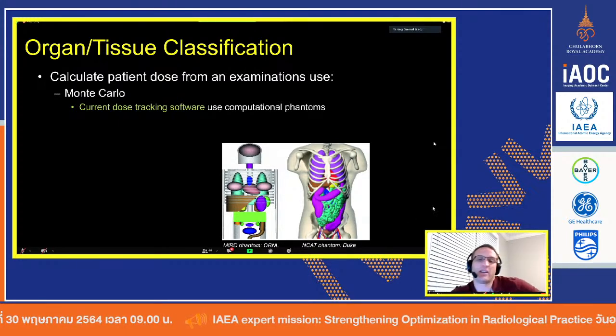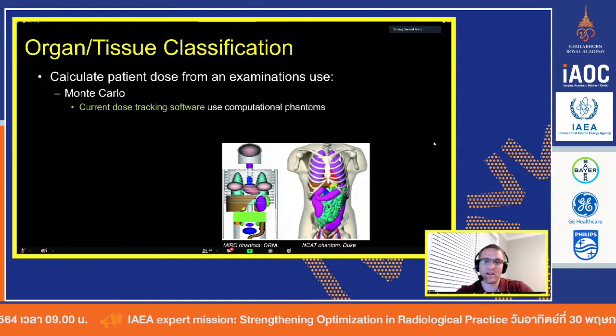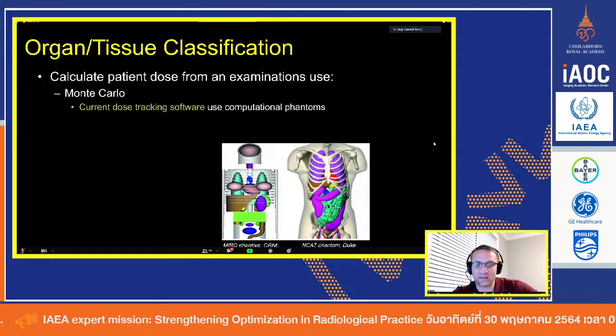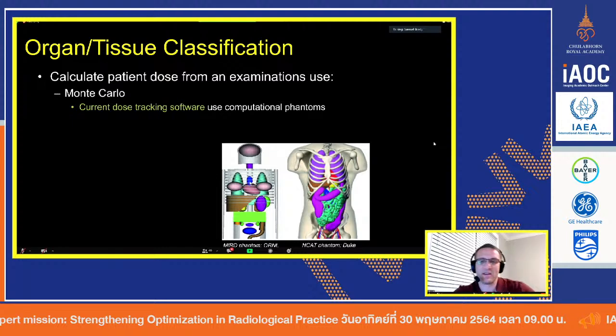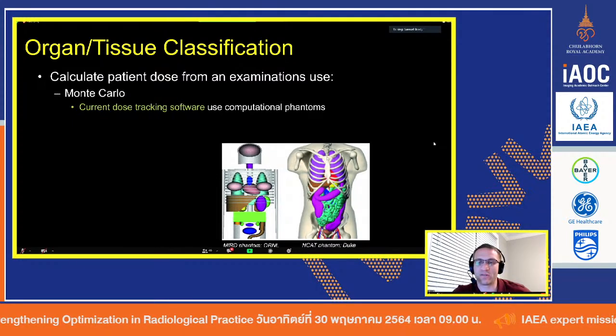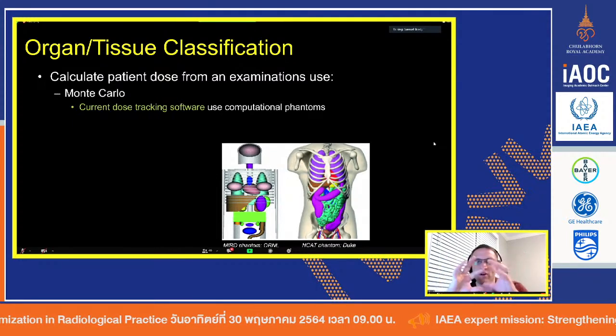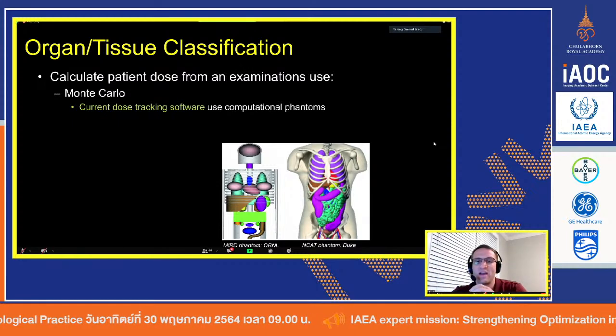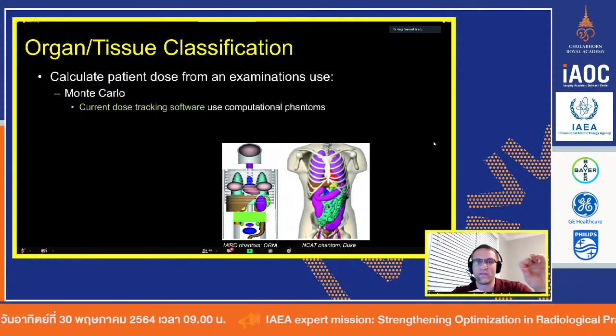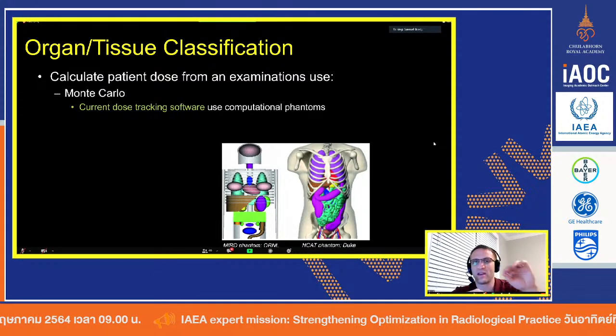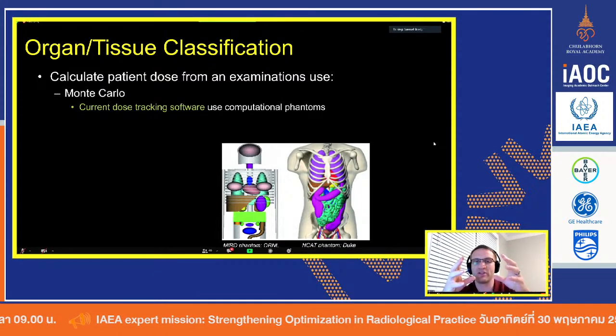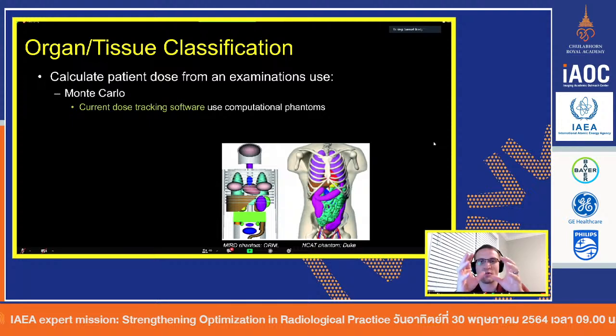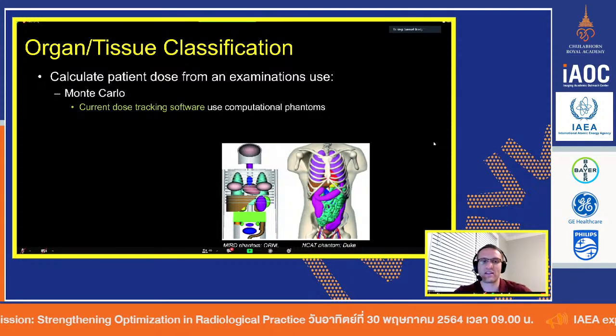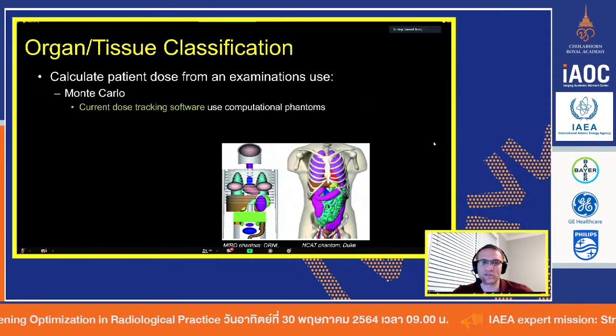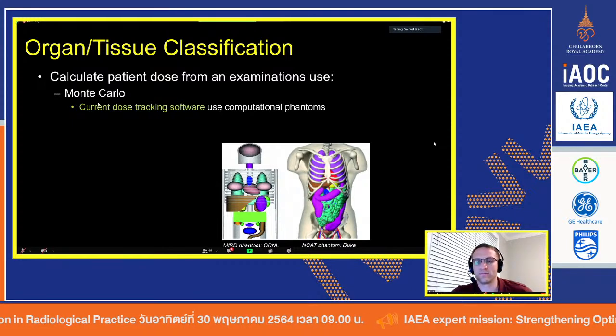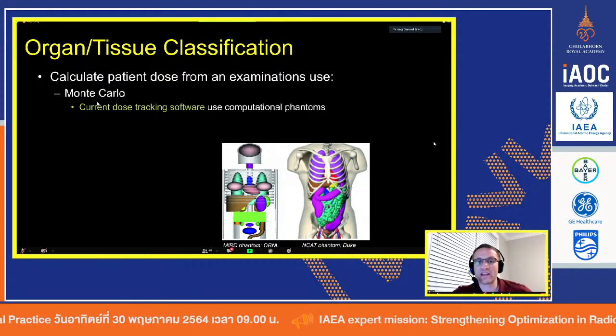And what it'll do then is measure how thick it is, and it will then pick a phantom of similar size, and it will have all of these organs already established, the volumes, the sizes, the lengths, all that. And then it will use the CTDI-vol and the mAs and the kV. It'll look at all of that information that came across from the structured dose report, and it'll use that to calculate the actual organ doses based on Monte Carlo lookup tables. So that's great.